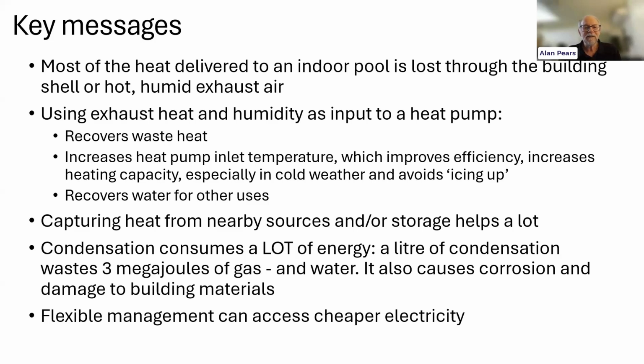I keep coming back to the issue that condensation can consume a lot of energy if you're condensing a lot of water on single glazing or other elements of your building, because evaporating water and then losing it is very energy intensive. Anyone who's been burnt by steam instead of hot water knows there's a lot more energy in water vapor than in liquid water. Condensation tends to happen on cold surfaces, which can be structural components and building materials, giving you a maintenance issue to think about.